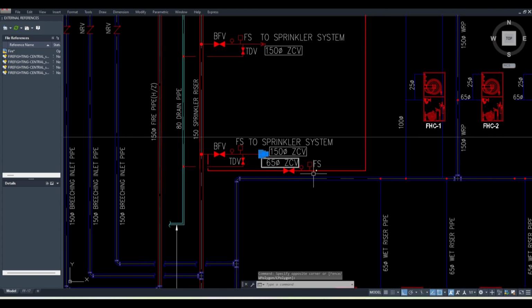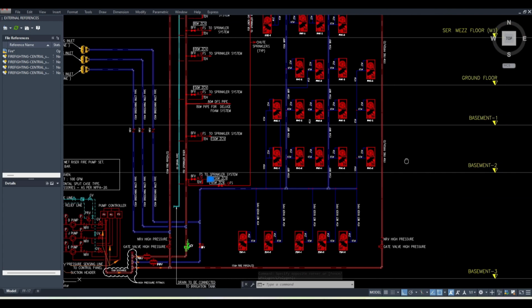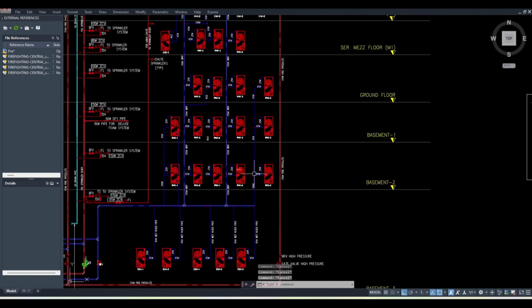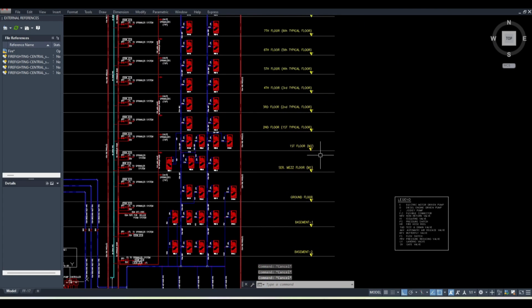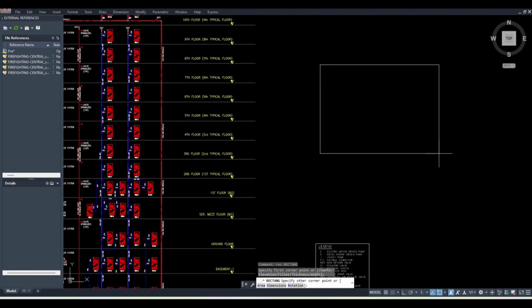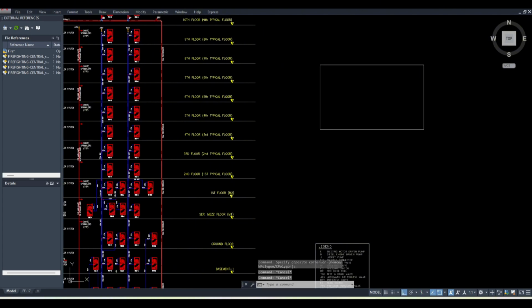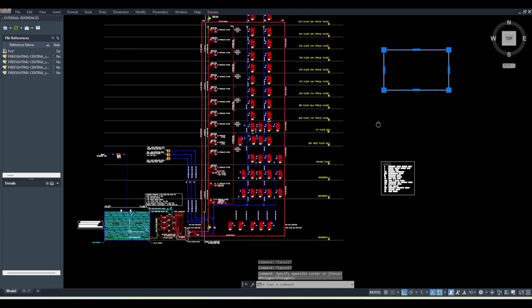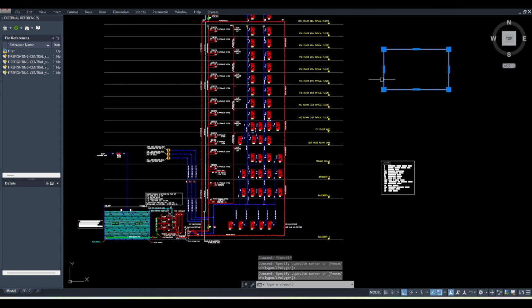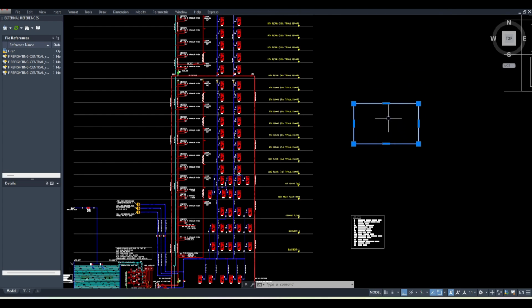Okay, design density. So based on that design, this depends on which class of building it is. Why that is not important for us: they choose that they need, like, 1500 square feet of area to be covered by the sprinkler. So based on that, if they have the K factor 5.6, they will multiply it and get the flow rate for this area. If they can achieve that area at the remotest location of the building, that much flow rate is required. Now this changes based on the building type and the application of that area, what kind of area it is.